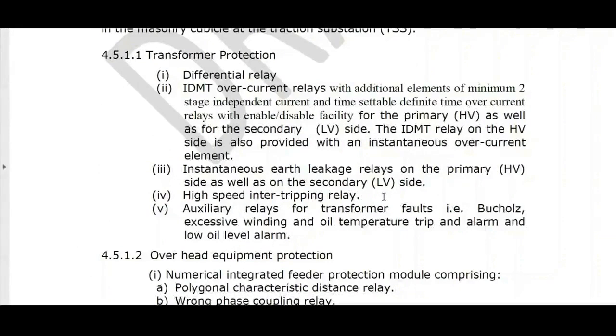High-speed intertripping relay. So this is not a protection function. It is an additional function used to help the protection function. Normally we call this the master tripping relay. The last one is auxiliary relays for transformers.